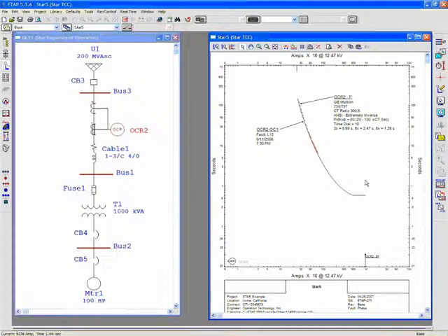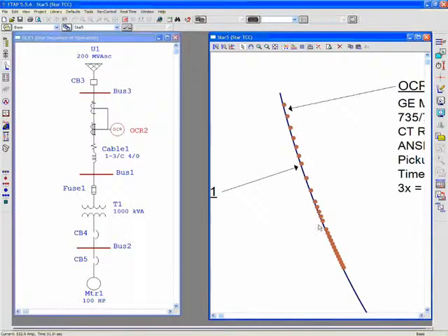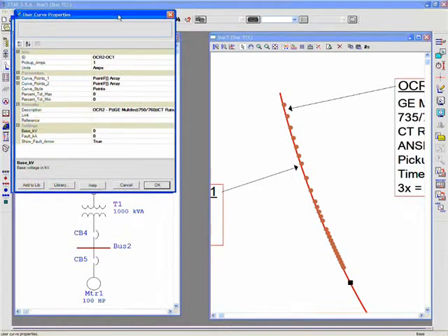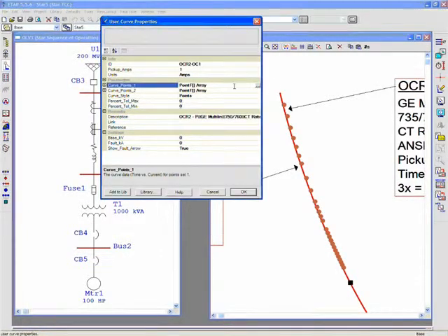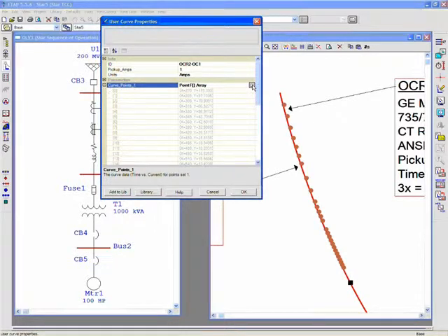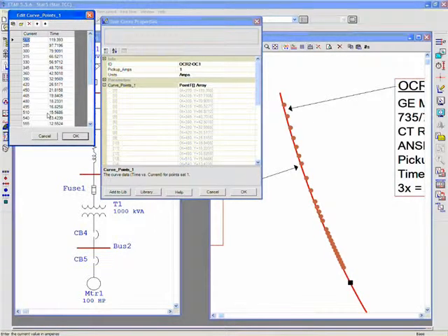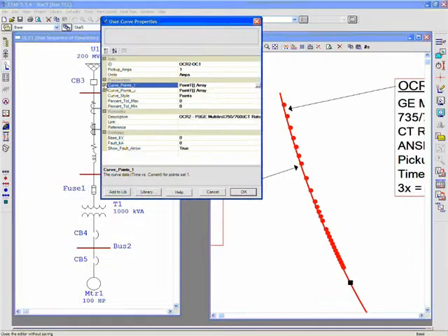which was used to compare a portion of this curve against the manufacturer published data. And as you see, the deviation is fairly small. You can zoom in here and see this even closer to see how the points are. You can double click on the points and bring up the points as a user curve. And you actually can expand on the points and see the actual point set that was generated for this test. So you can at any point go in there and modify the points, delete some points, or you can do it directly from the database or from ETAP.